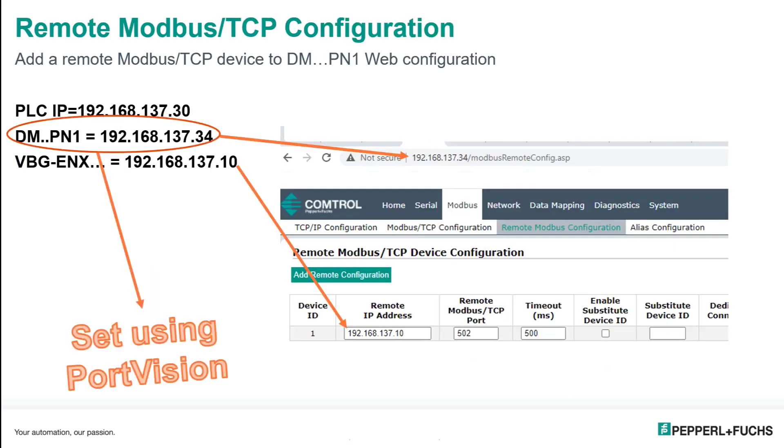So the first thing you want to do is use PortVision. This is a very simple and free protocol software that you can use to set your IP address. So once the IP address is set, put it in your browser, make sure you're in the same subnet, and you're going to have your configuration utility without any extra software.